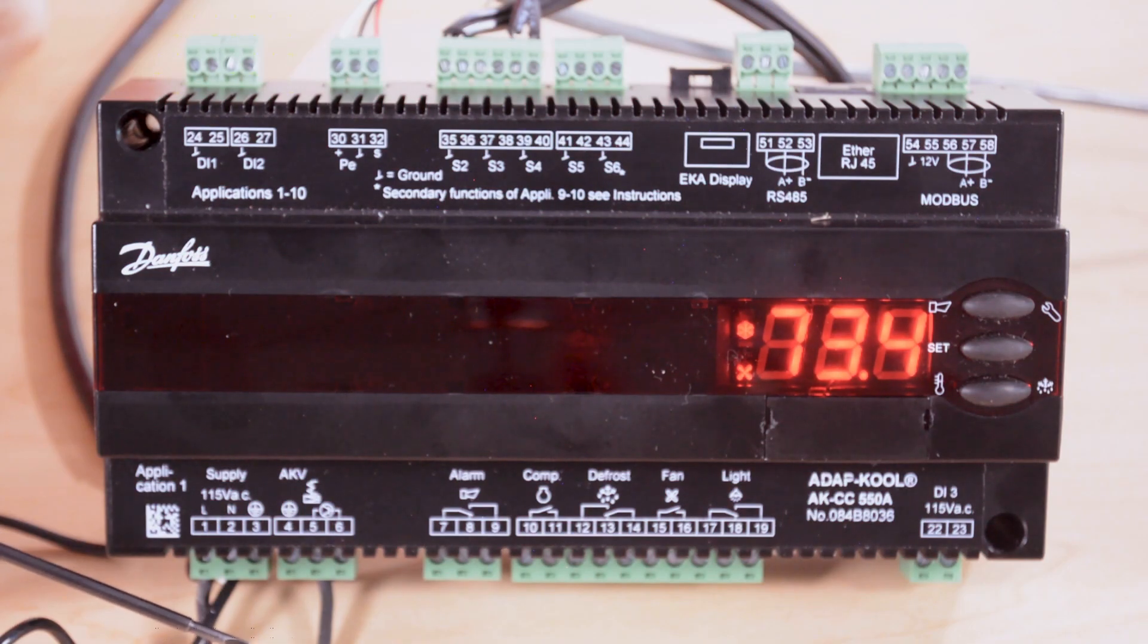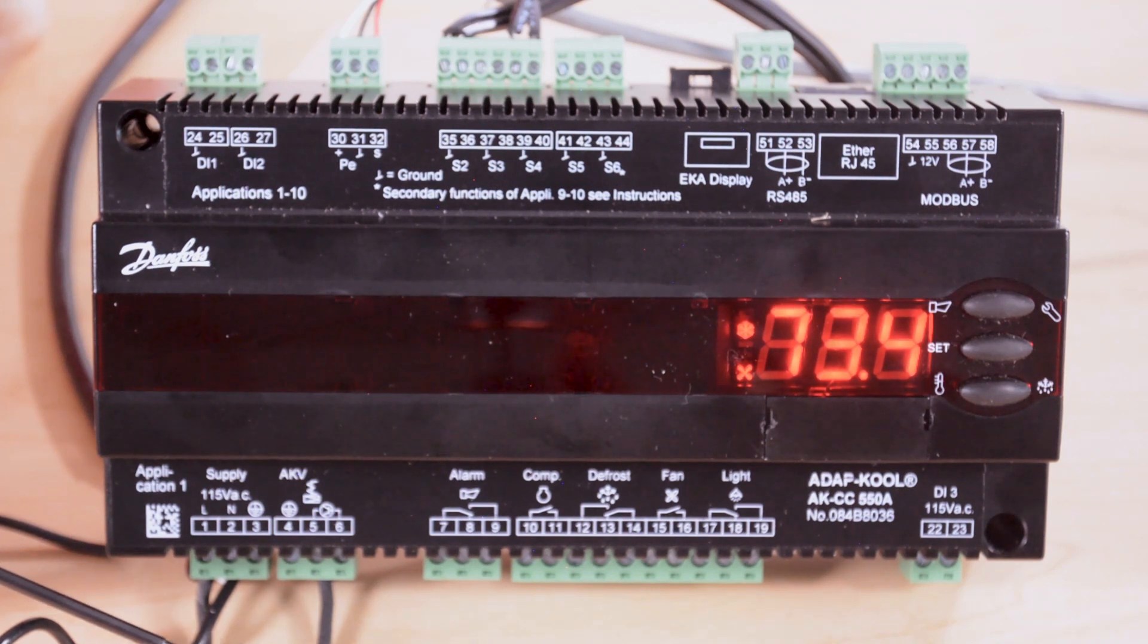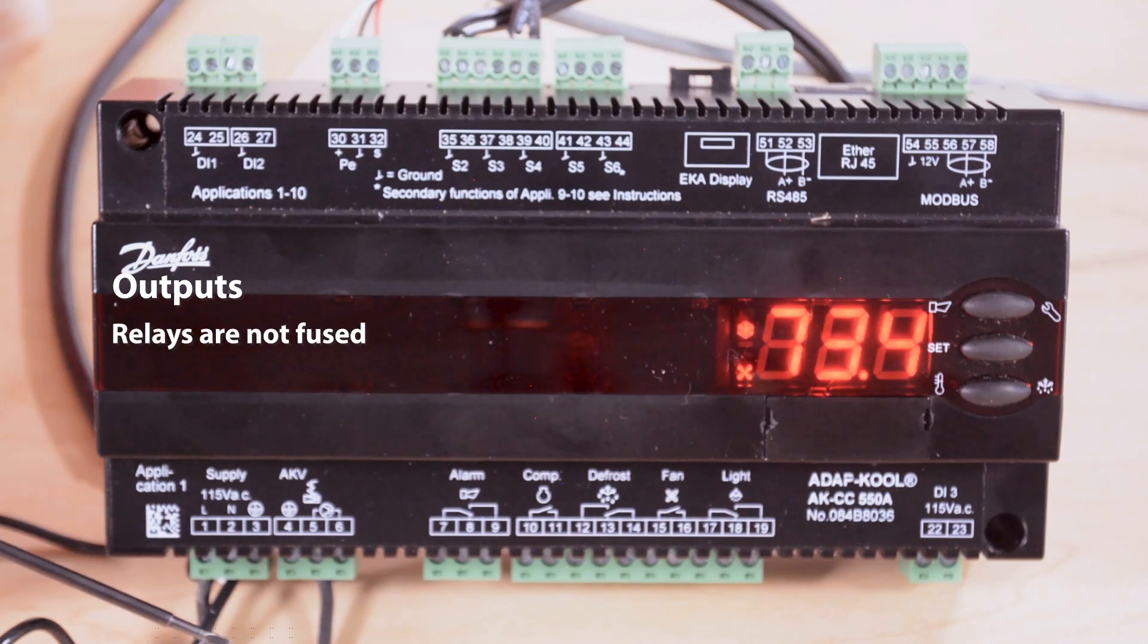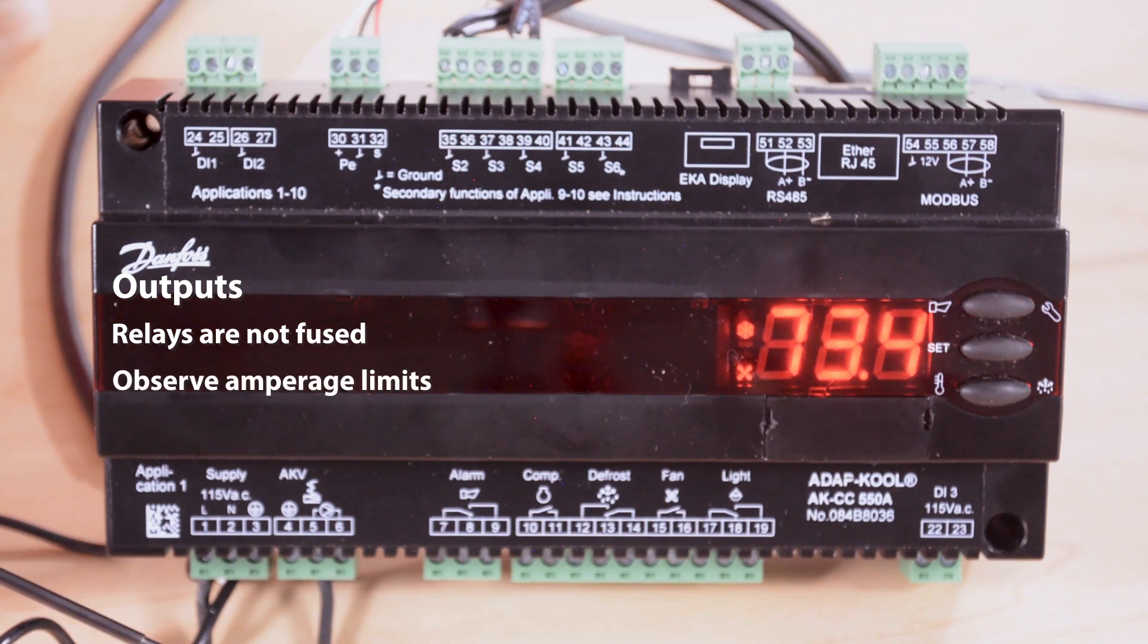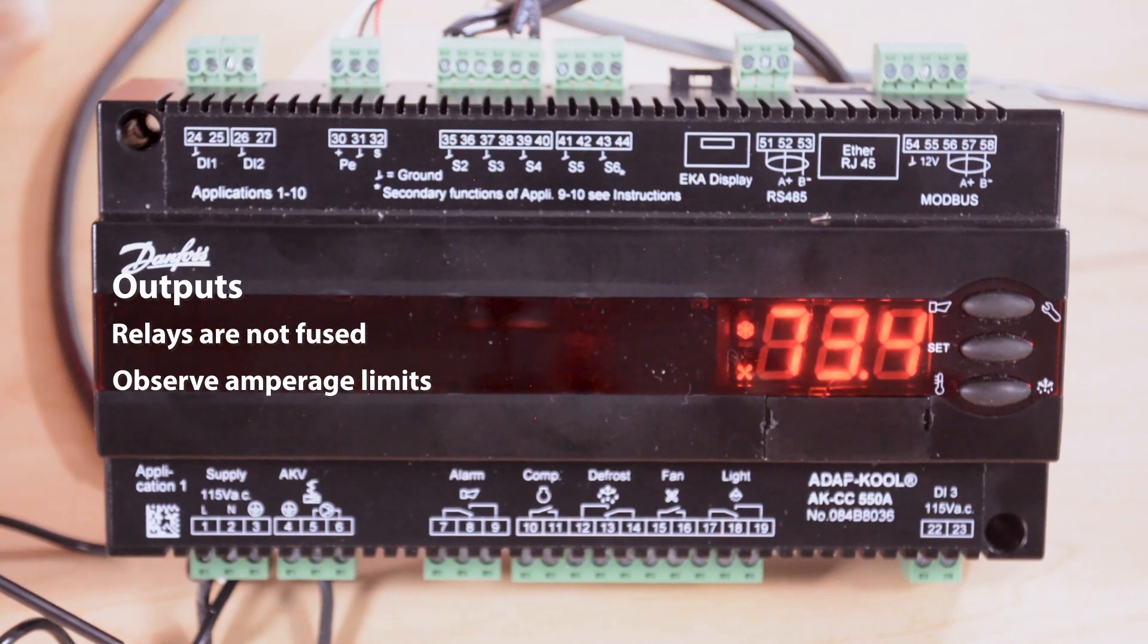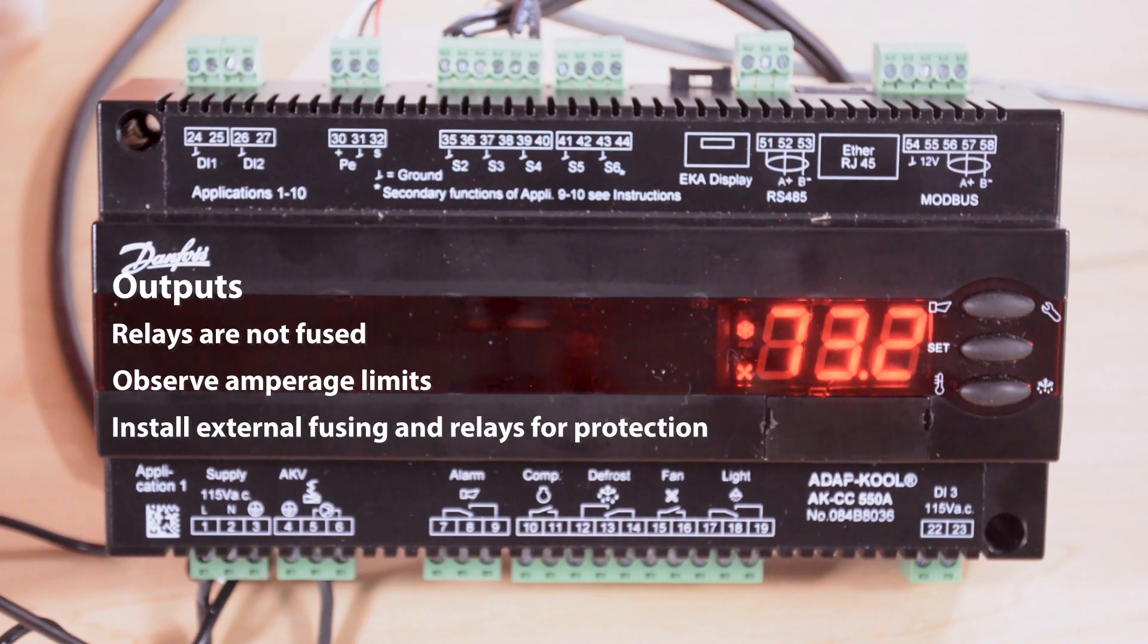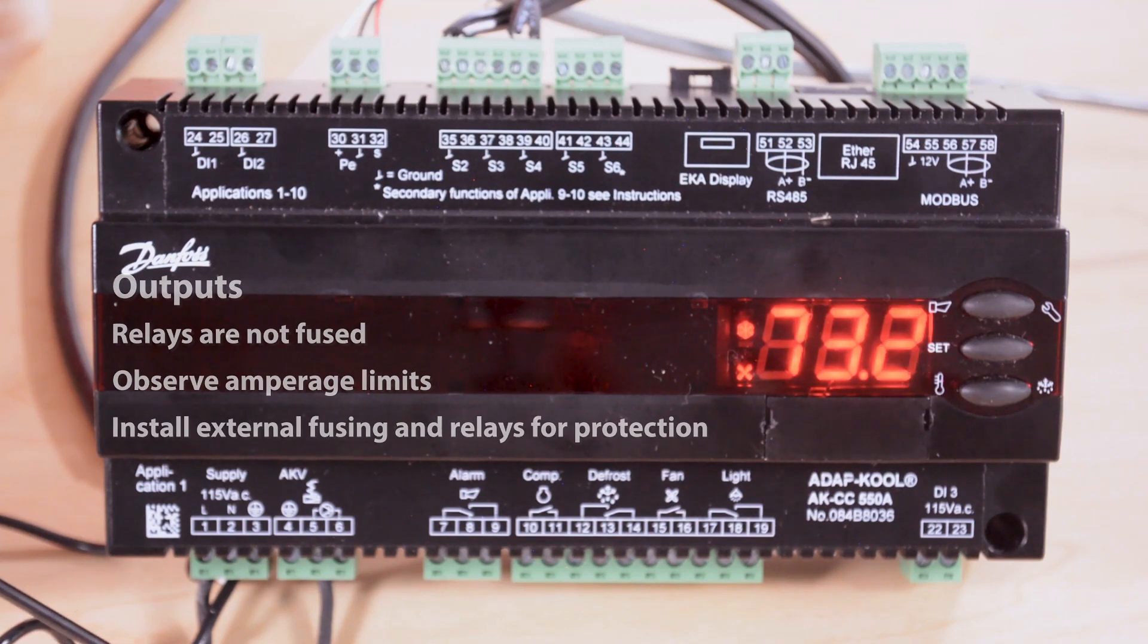The only connection here that's done normally closed typically would be the fan relay. Of course the rest would be normally open. Since these relays are not fused internally all fusing would be done external to the controller. The relays inside this controller have current limitations so typically pilot relays are used to control the loads and they're wired between this controller and the load itself to meet the demands of inrush current and running load amps.